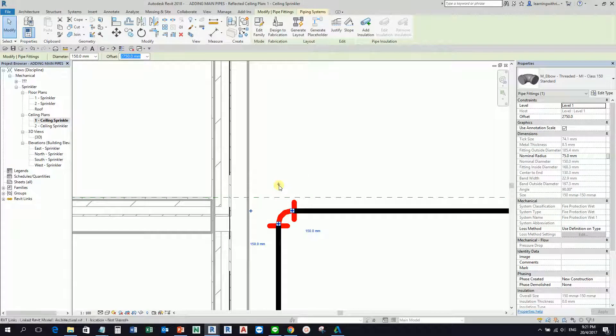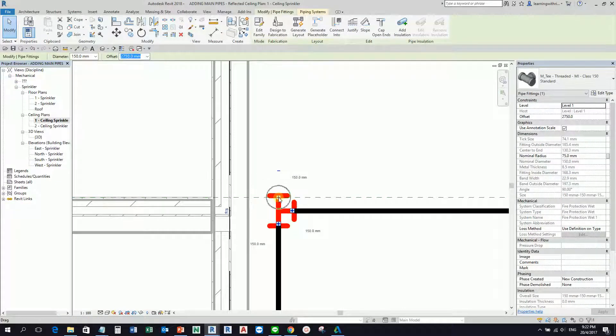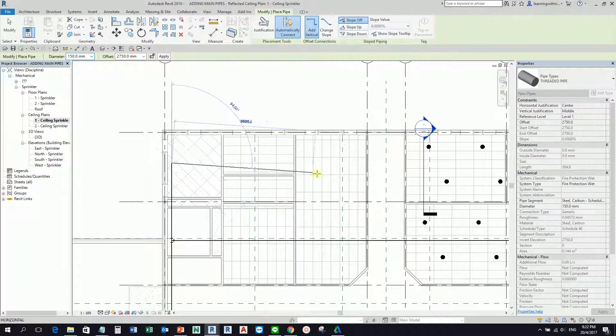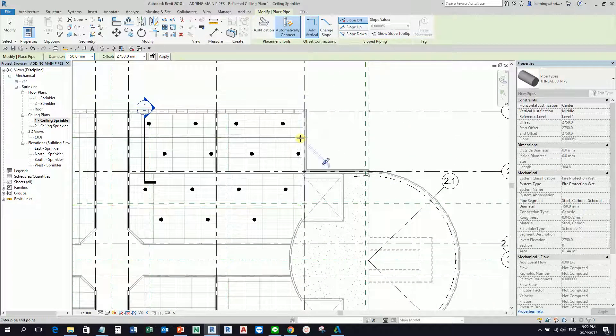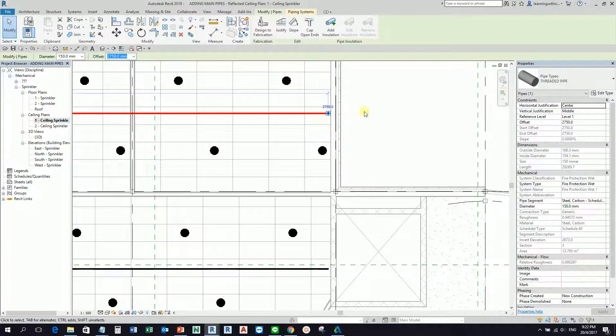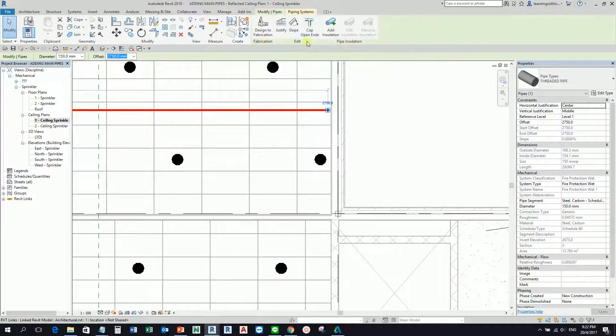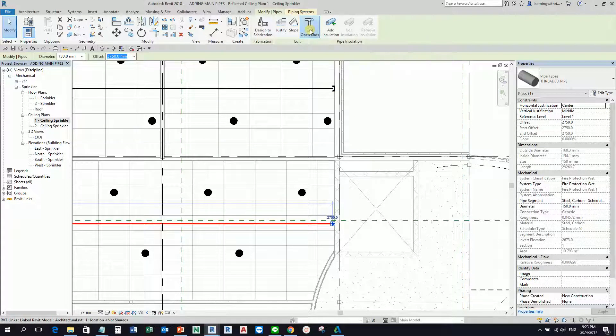Now I want to place another pipe. I'll select this fitting and click the plus sign, which allows me to change the elbow to a tee fitting. I select the tee fitting — you see the connector — right-click it and select Draw Pipe. I'll approximate a location and place it along here. One great thing about newer versions of Revit: instead of placing an end cap manually, you just select the pipe, click Open Ends, and it automatically places the end cap for you.